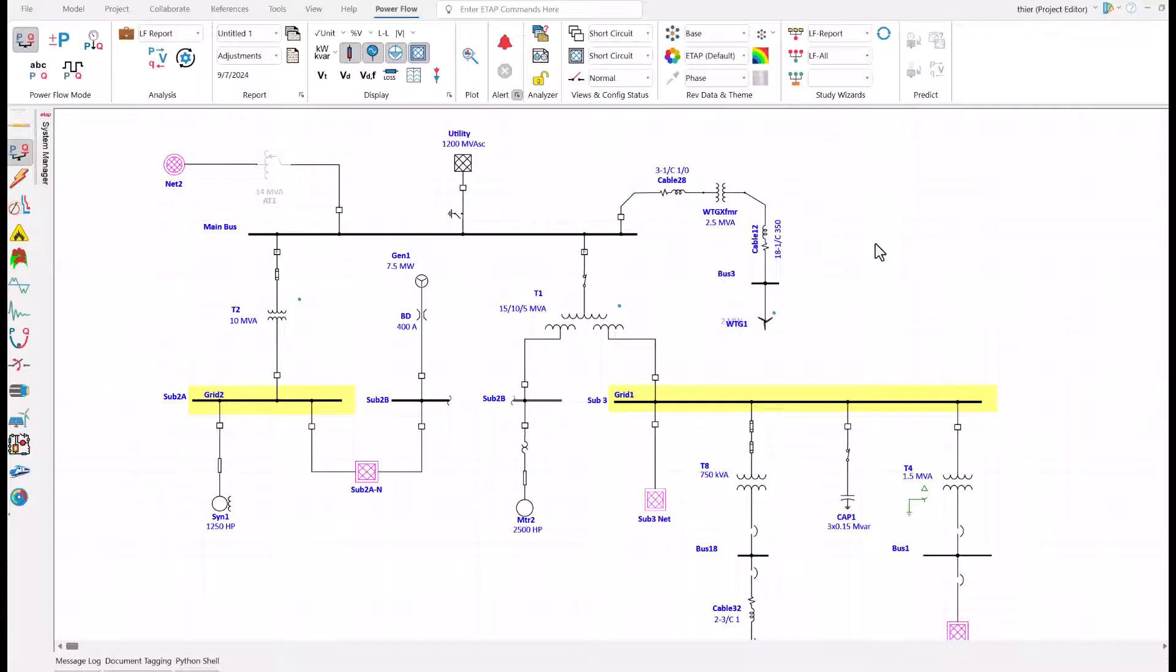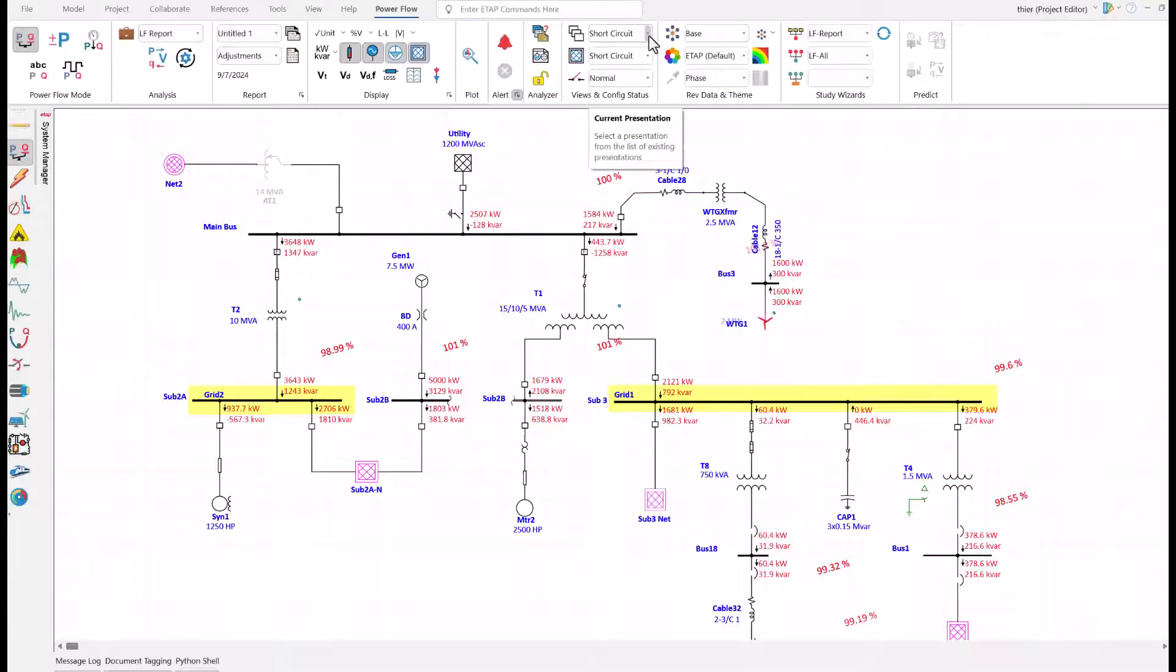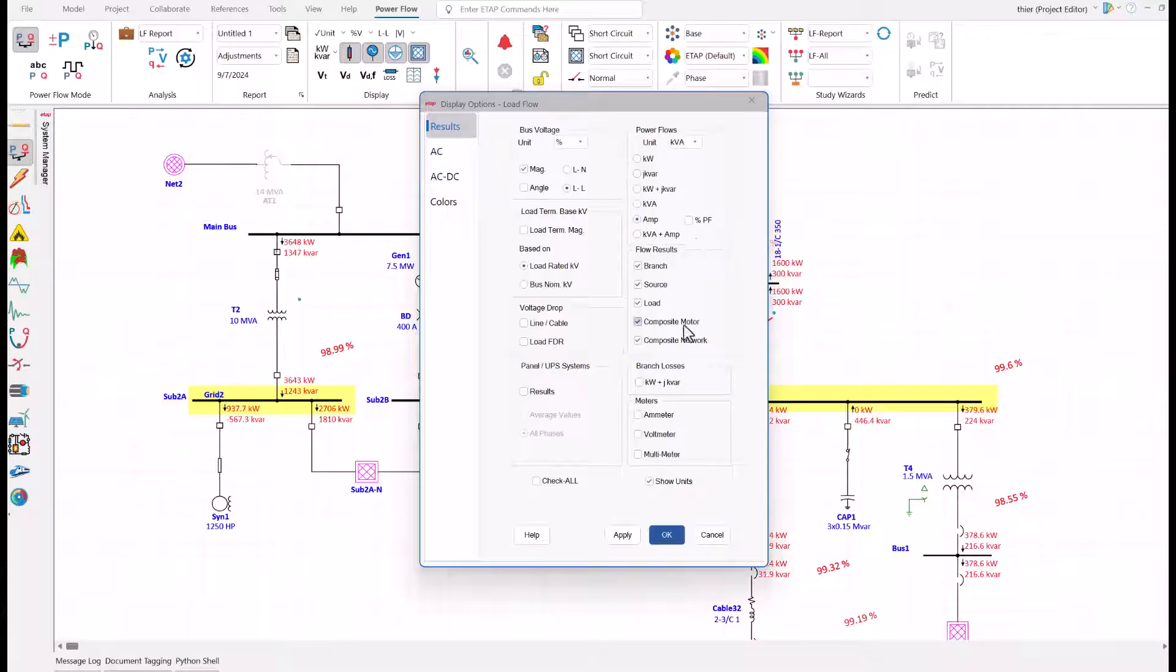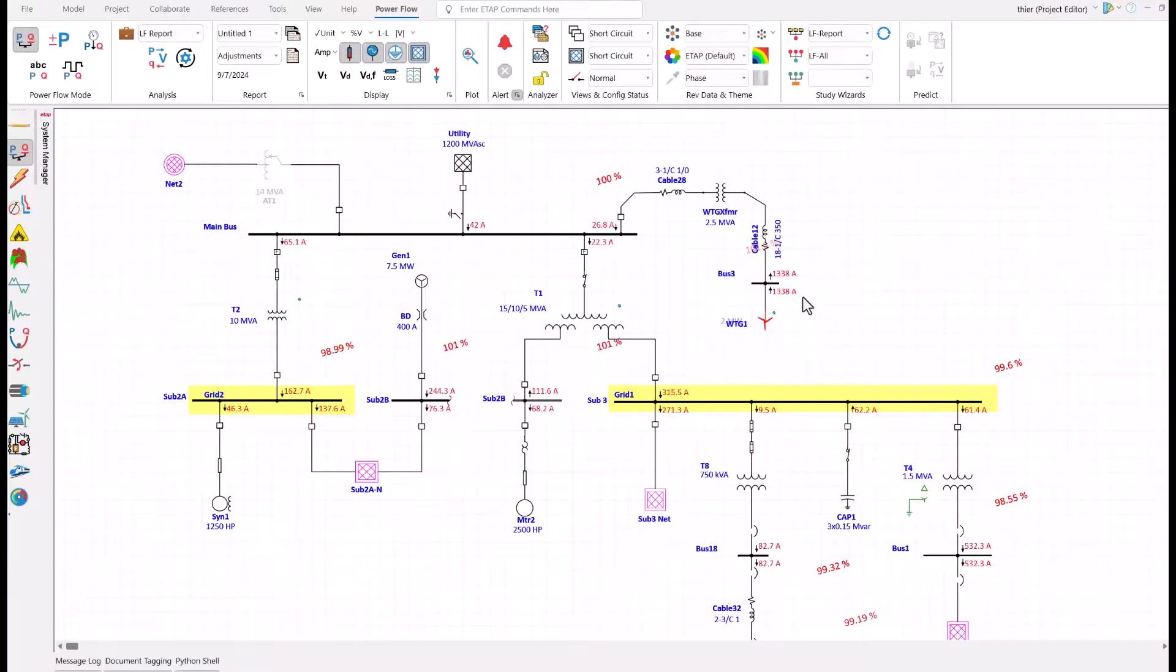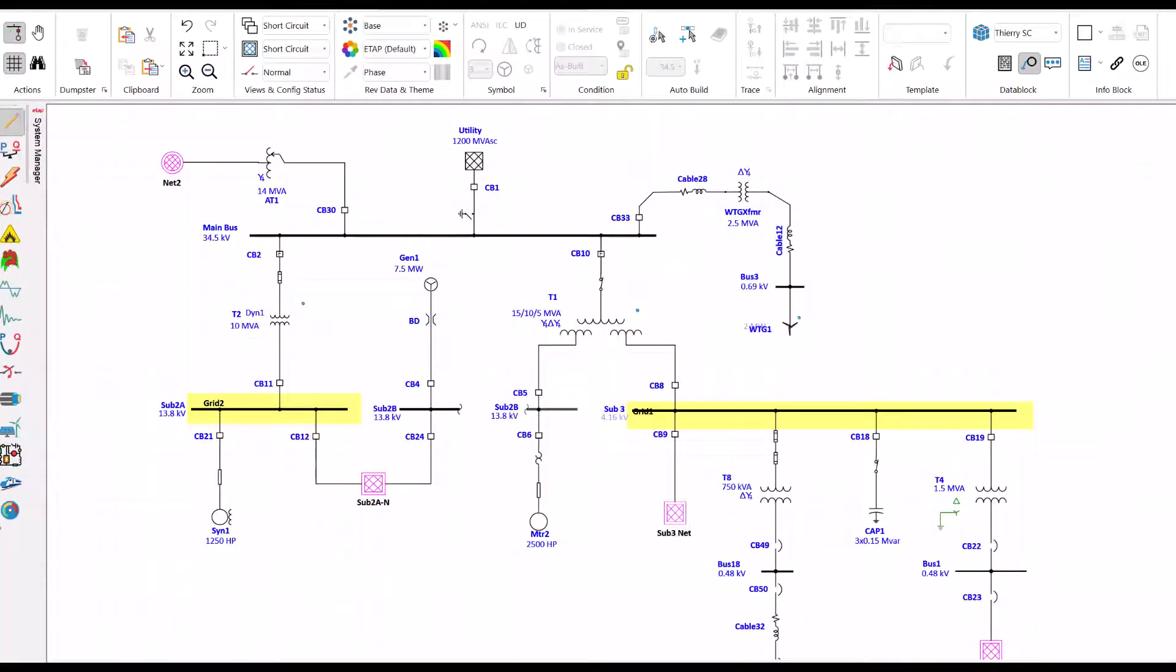I click on the power flow group, then run load flow. We can see kilowatt flows from the utility, from the turbine, all the way down to the loads and other substations. We can switch the data and see the amps: 42 amps from utility and 1,338 amps from wind turbine. At this point, the audience has a basic understanding of their facility, the power source and their loads. Everyone is focused. We are on the same page electrically.